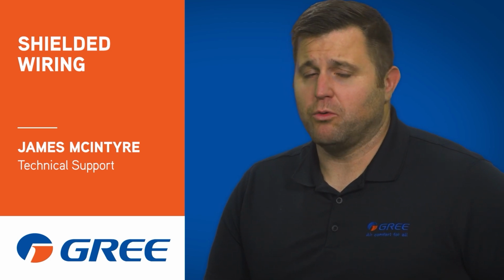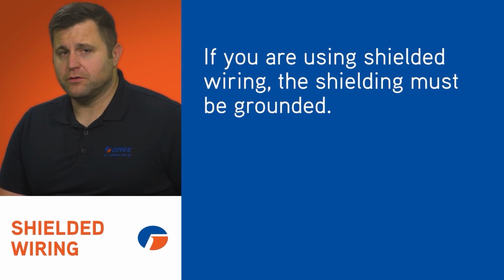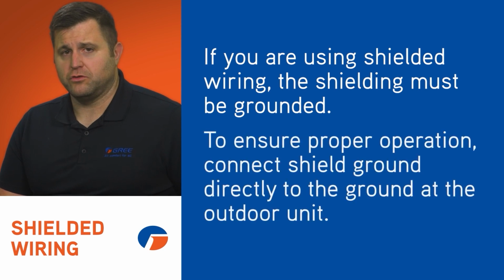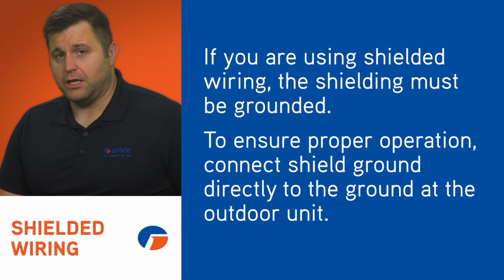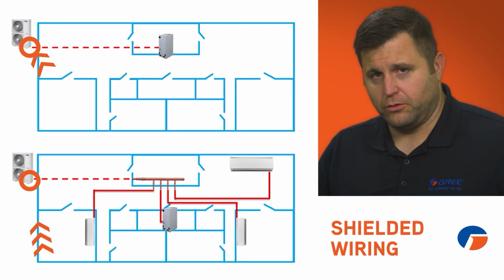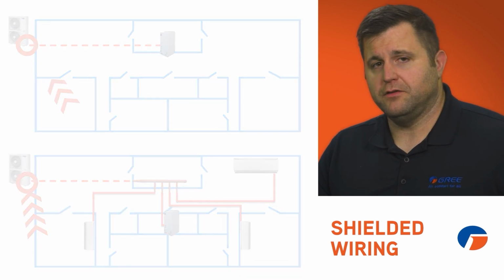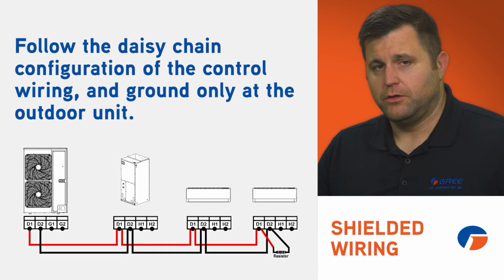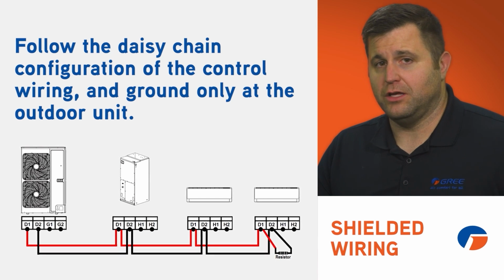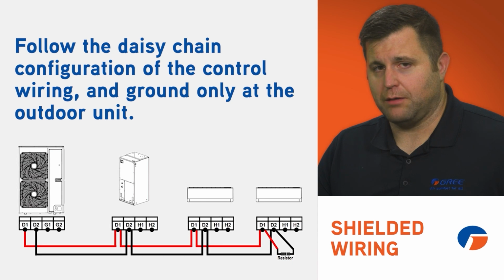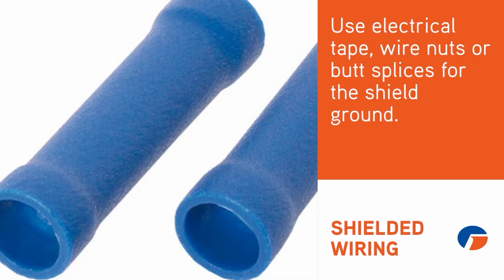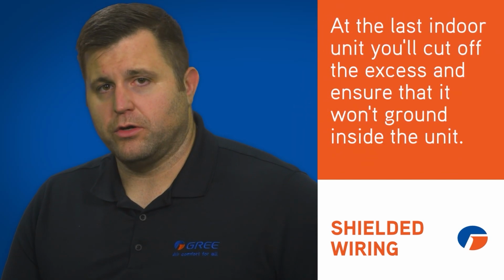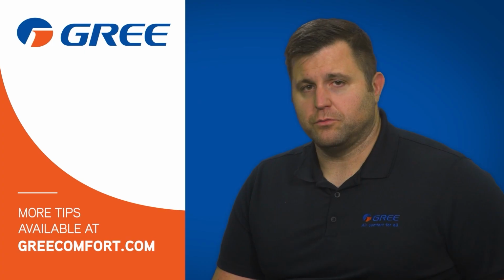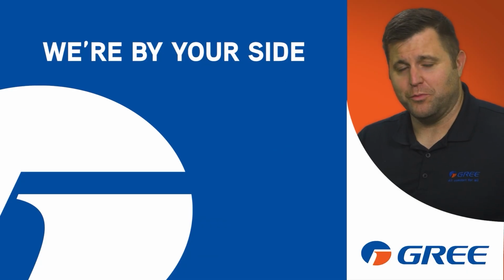Let's talk about shielded wiring. Shielded wiring is recommended on jobs that may have a large amount of noise, but we do not require its use. If you are using shielded wiring, the shielding must be grounded. In our case, to ensure proper operation, you'll take the shield ground, which is normally a silver-colored uninsulated wire, also known as a drain, and connect it directly to the ground at the outdoor unit, and at the outdoor unit only. For single zone and multi-zone units, you'll ground the shielding at only the outdoor unit's ground. In the case of daisy chain communication, like what is found in our MultiPRO line, you'll ground the shielding at the outdoor unit, and tie the 2 grounds together at each indoor unit without grounding them. Make sure they cannot touch the cabinet. We suggest using electrical tape, wire nuts, or butt splices for the shield ground itself. At the last indoor unit, you'll cut off the excess and ensure that it won't ground inside the unit. This ensures proper operation of the unit. Thanks for watching. At GREE, we're by your side.